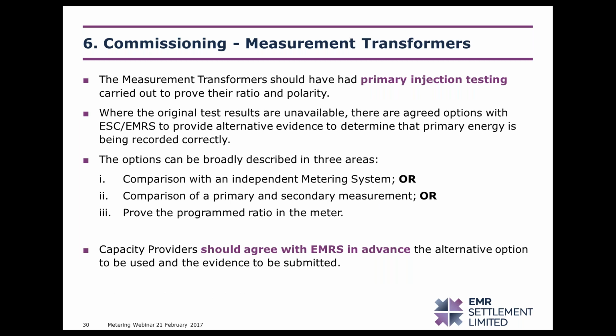Turning now to the second part of the commissioning, which is the measurement transformers. Measurement transformers are installed in switchgear, which should have had, during its site acceptance testing, primary injection performed on it with a known load. This is to prove that the ratio and polarity of connected measurement transformers, this is both current and voltage transformers where applicable, is correct. Evidence of this original testing at the time of installation is acceptable to meet compliance with this part of the metering test.